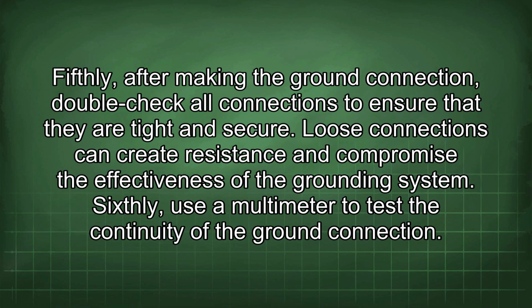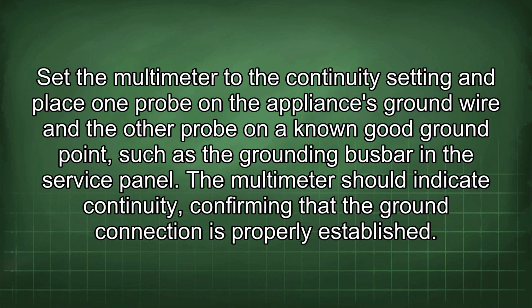Fifthly, after making the ground connection, double-check all connections to ensure that they are tight and secure. Loose connections can create resistance and compromise the effectiveness of the grounding system. Sixthly, use a multimeter to test the continuity of the ground connection. Set the multimeter to the continuity setting and place one probe on the appliance's ground wire and the other probe on a known good ground point, such as the grounding busbar in the service panel. The multimeter should indicate continuity, confirming that the ground connection is properly established.